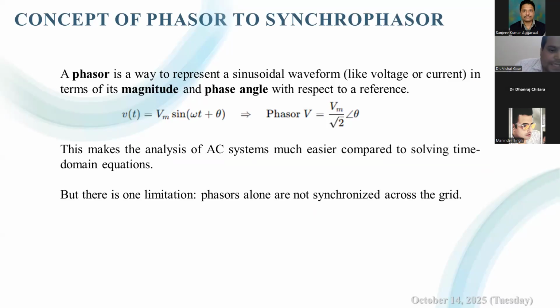But here there is an important limitation: phasors alone are not actually synchronized across the grid. For example, if I measure a phasor in Delhi and you measure another in Mumbai, our measurements are referenced to our local clocks. So the phase angles cannot be compared directly because the reference time may be different due to the difference in the local clocks. It means we need to measure the phasors with reference to a common clock, a common reference clock.